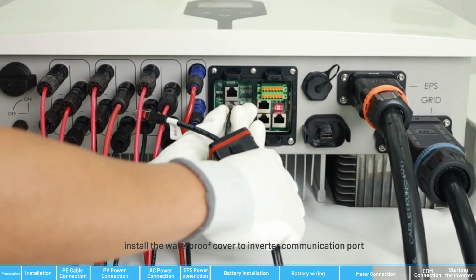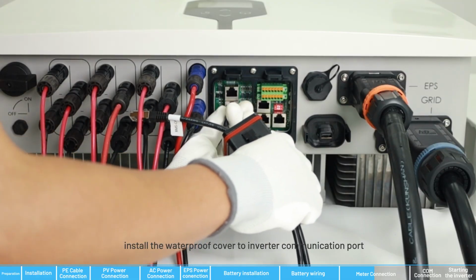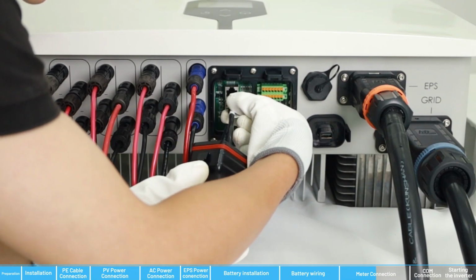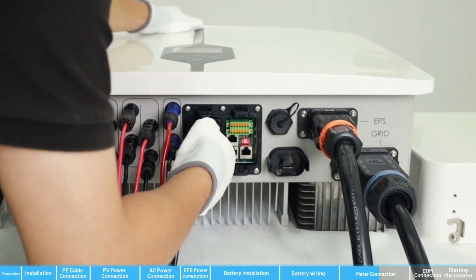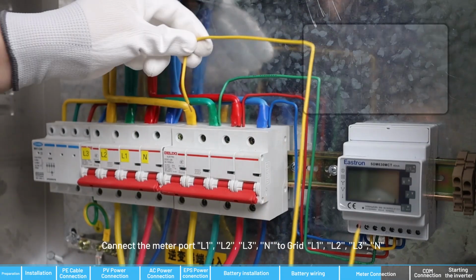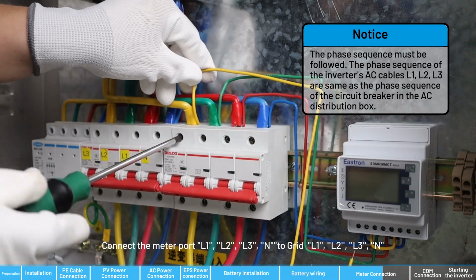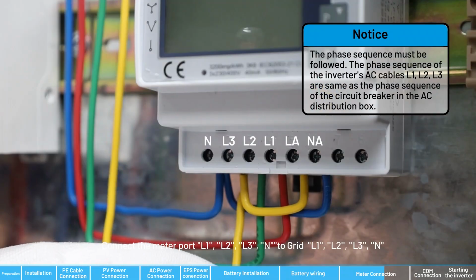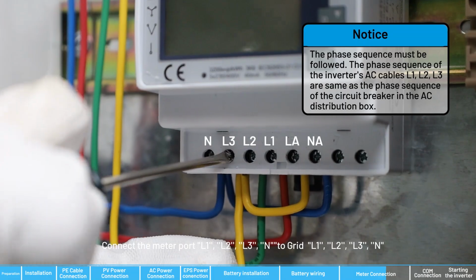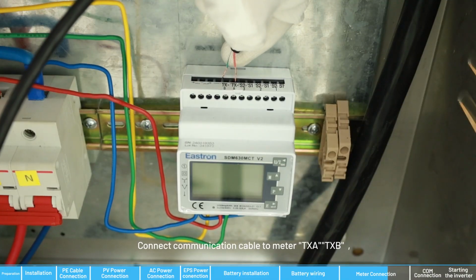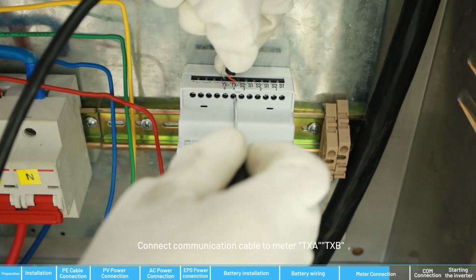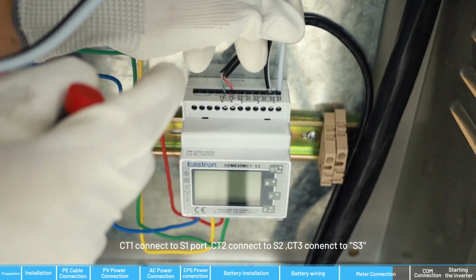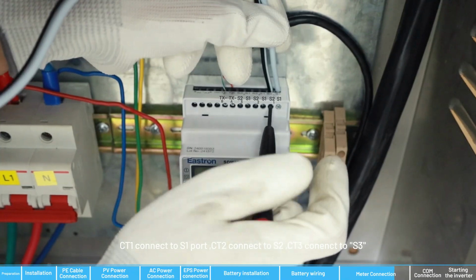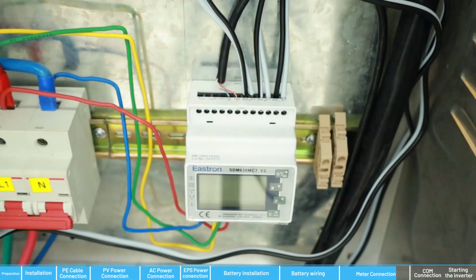Install the waterproof cover to inverter communication port. Connect the meter port L1, L2, L3, N to grid L1, L2, L3, N. Connect communication cable to meter TXA, TXB. CT1 connect to S1 port, CT2 connect to S2, CT3 connect to S3.